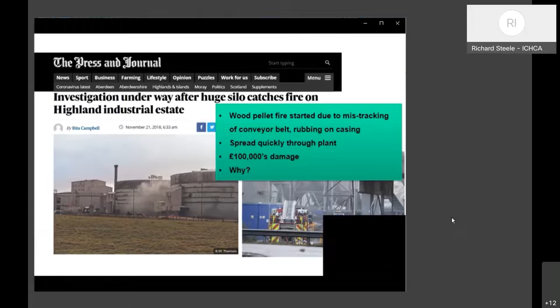Why was that not detected? For this equipment to be suitably ATEX rated for use in this zone, it was fitted with belt tracking sensors. Because the belt tracking sensors are your prevention of frictional heating. And the belt tracking sensor is a protective device, shall we say. But for some reason it failed. And the reason that it failed was because when we walked around that plant after the incident, we found a lot of sensors like that, heat sensors on bearings, belt tracking sensors and so on. They'd been installed but never connected. So the sensors were there and the wires were just hanging, never been hooked up. And for half a year since commissioning, people have walked past those and never asked, why are these sensors not connected? Now, can you believe that? So where you've got sensors, you've got to make sure they're properly connected.